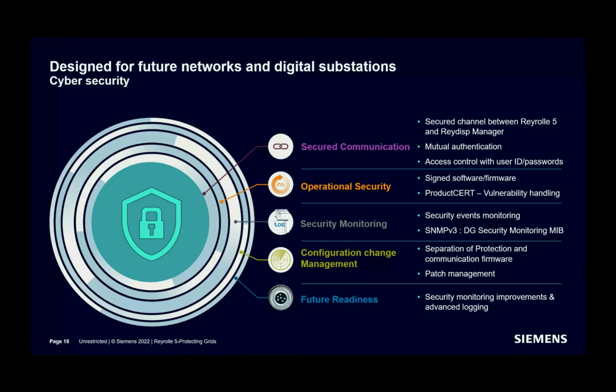Cybersecurity-related events like login attempts or device records are recorded and optionally transmitted to a central server via standardized syslog UDP protocol. So you just only enter an IP address. It's actually a redundant IP address inside the software. You upload the configuration, and that's it. All the security-related logs are recorded and sent via syslog UDP protocol automatically all the time to the defined IP addresses.